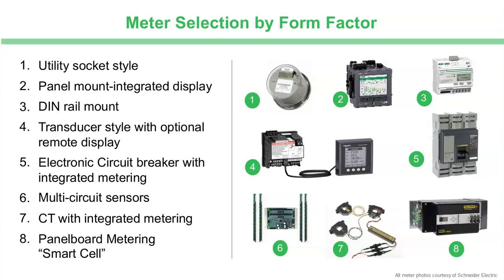One thing to always keep in mind with those types of meters is all of these circuits need to be from the same source. You would not want to put this as a meter to monitor circuits in different panels. Generally, it's everything within that panel is the way that you would go, and it's all from one common voltage input, single phase or 3-phase.